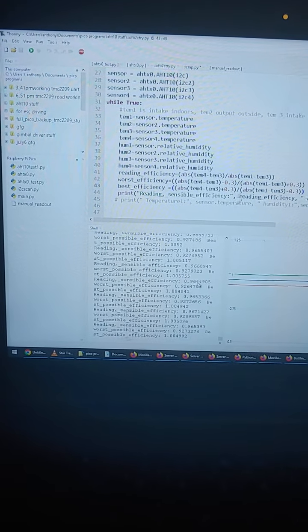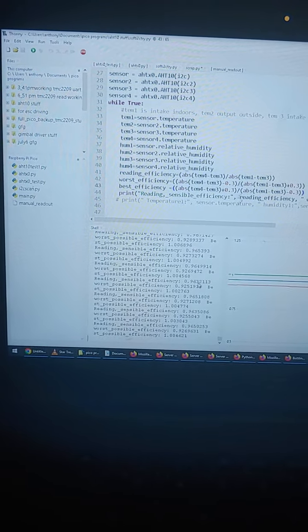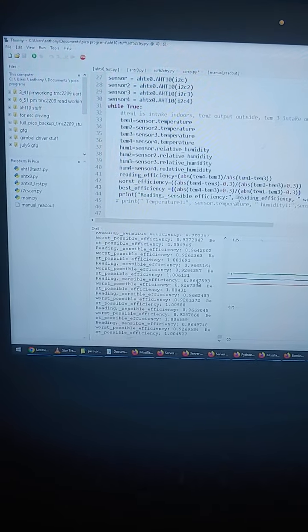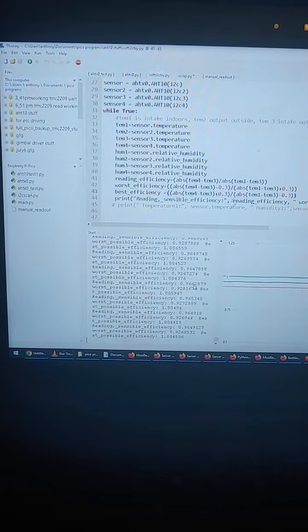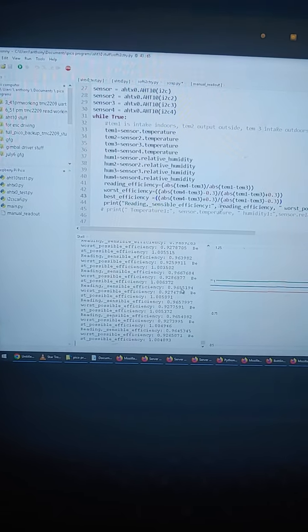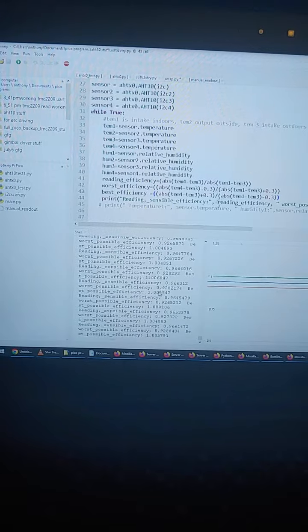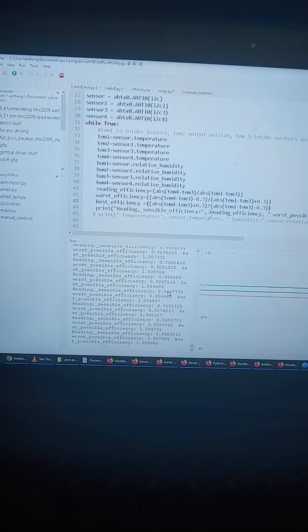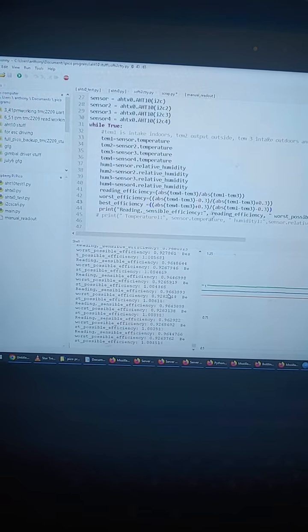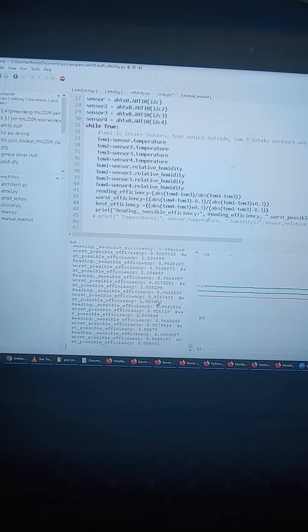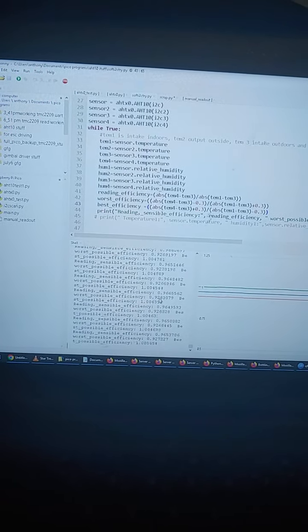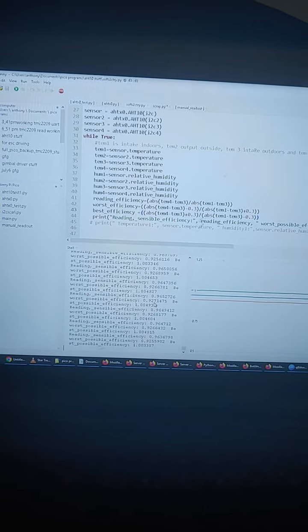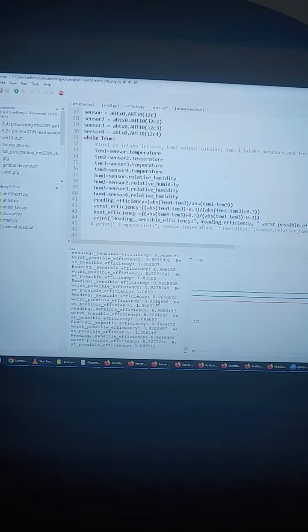Now this is the naive assumption of what the efficiency of the system is, I mean 96%, which is not entirely, it can't be quite right, but if the temperature sensors were reading in the worst possible way, it would be about 92% based on the temperatures of the airflow.